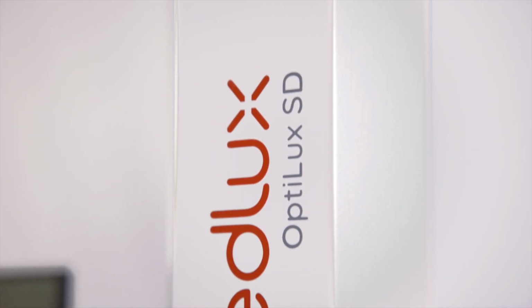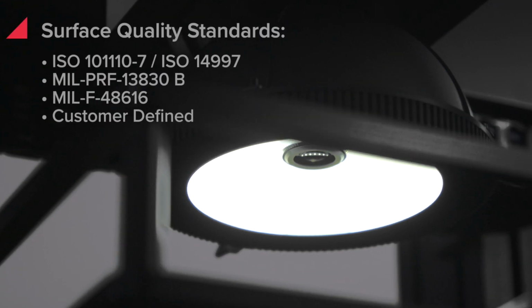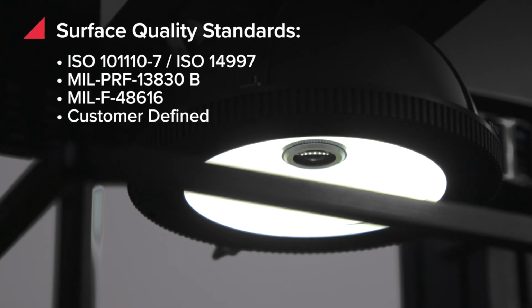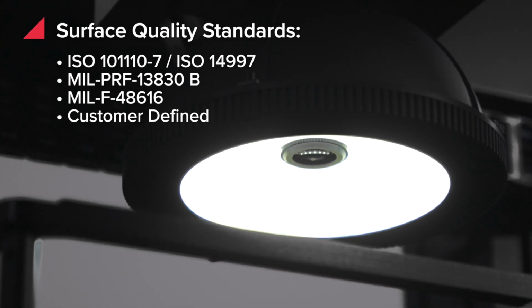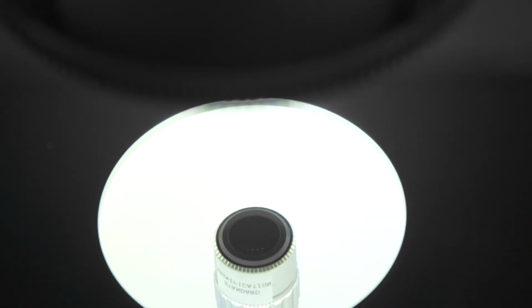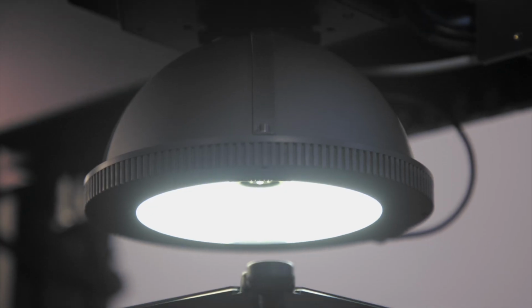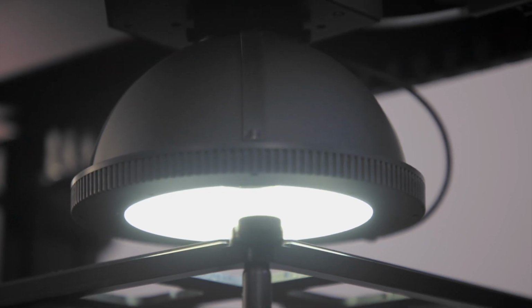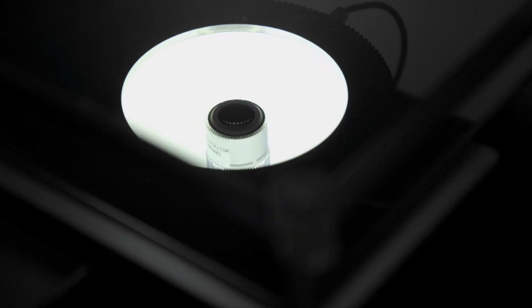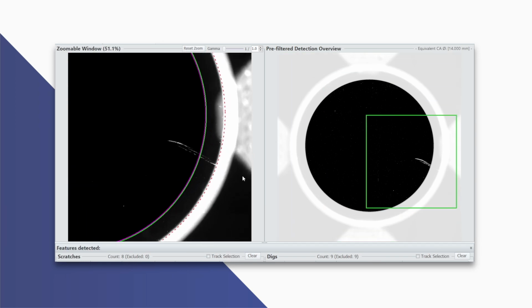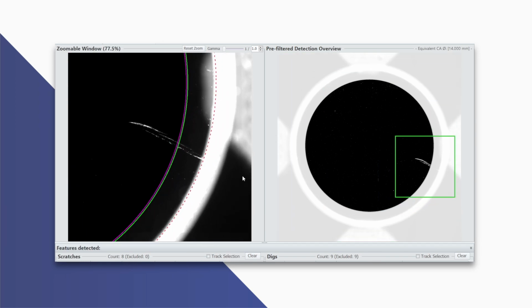Capturing calibrated, traceable, and objective inspection data, OptiLux SD's patented inspection technology supports both cosmetic and dimensional analysis of surface imperfections, offering comprehensive coverage of the applicable standards from a single device.